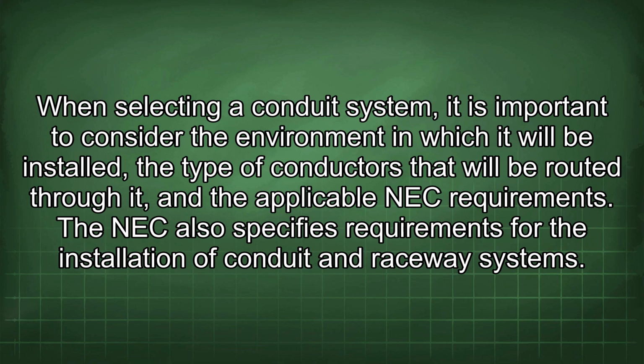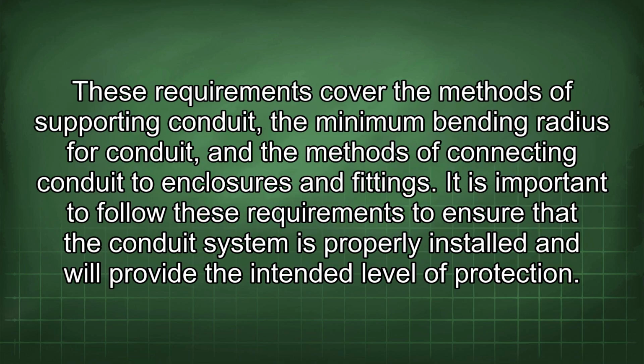The NEC also specifies requirements for the installation of conduit and raceway systems. These requirements cover the methods of supporting conduit, the minimum bending radius for conduit, and the methods of connecting conduit to enclosures and fittings. It is important to follow these requirements to ensure that the conduit system is properly installed and will provide the intended level of protection.